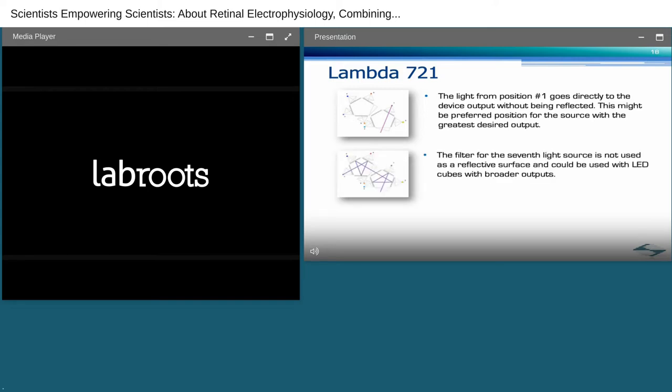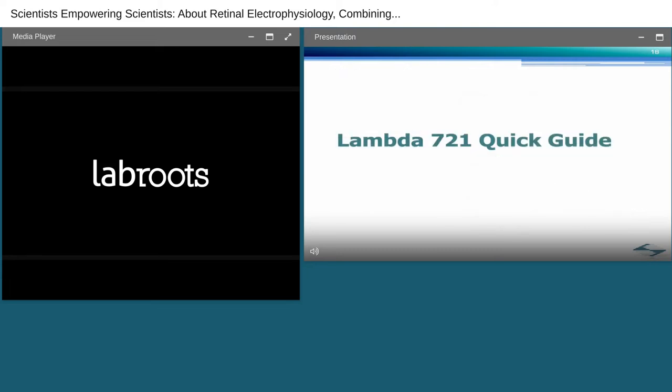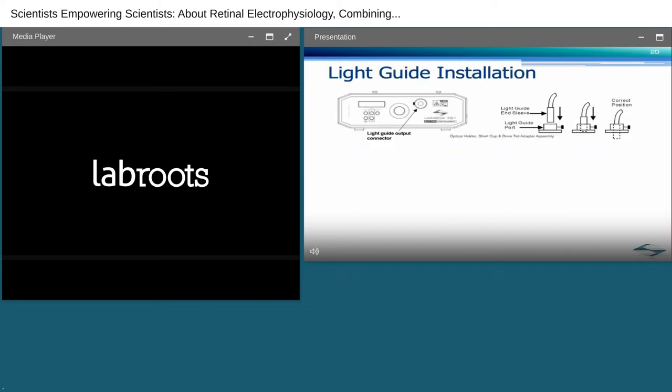Even though specific LED cube placement is not a requirement, here are a few suggestions for optimizing light output. The light from position number one goes directly to the device output without being reflected. This might be the preferred position for the source with the greatest desired output. The filter for the seventh light source is not used as a reflective surface and could be used with LED cubes with broader outputs. In configurations with fewer than seven light sources, LED cubes should be filled from lowest to highest number of reflections to ensure the greatest possible light output. These are just suggestions as you can use any placement that works best for your experimental needs.